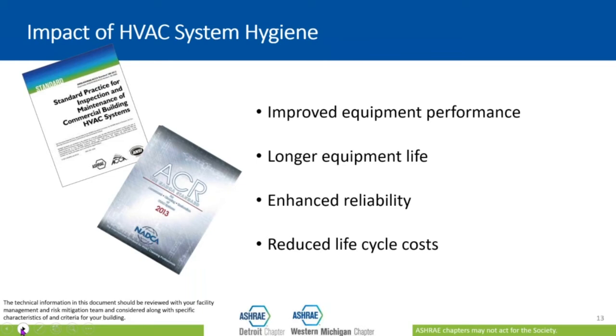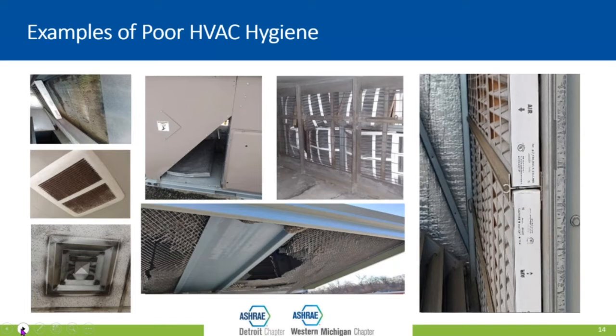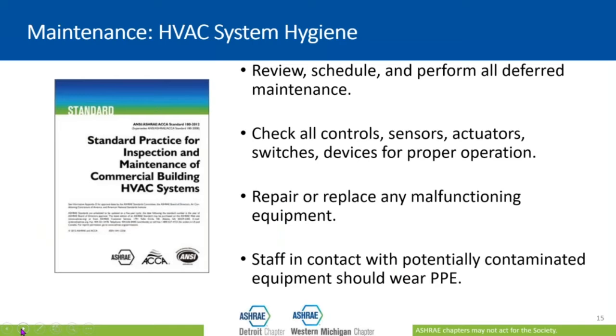And if you have any deferred maintenance, you want to make sure that you get that scheduled and get that work done. Usually when times are bad, the first budget that gets cut is maintenance. And when things are good, the last budget to be considered is maintenance. So very often we find our facilities with a lot of deferred maintenance that needs to be done. And so we want to make sure that we get that addressed. We also want to make sure that as we're doing that, we definitely check our actuators. We want to make sure that these things are properly calibrated. The last thing we want is to have a building automation system say the outside air damper is at 100% when it's really only at 50.